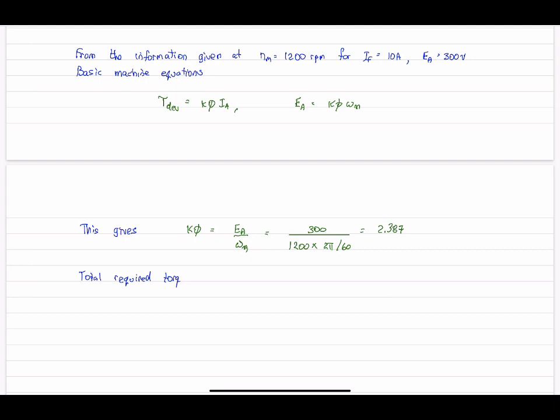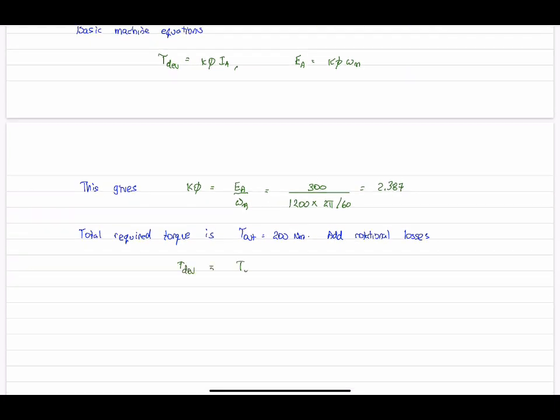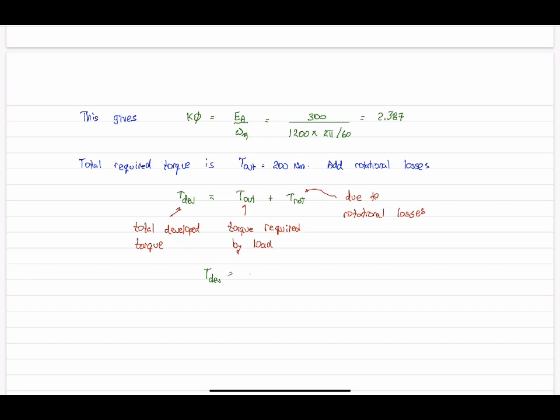Now the total required torque is 200 newton meters. So this is the torque that is demanded by the load, so we have to make sure we deliver that. What we need to do is calculate the total developed torque. So the sum of the required output torque by the load, and we have to factor in these rotational losses. So total developed torque needs to be 212 newton meters. So that guarantees that 200 newton meters are delivered to the load.